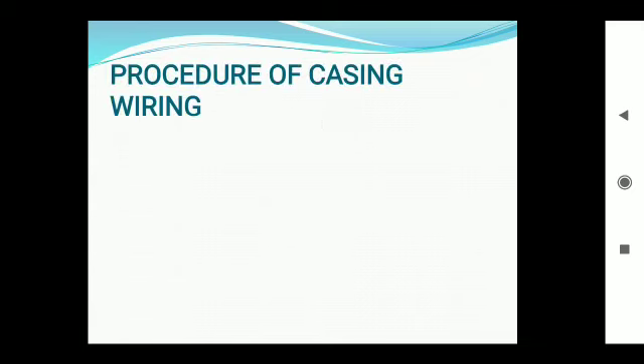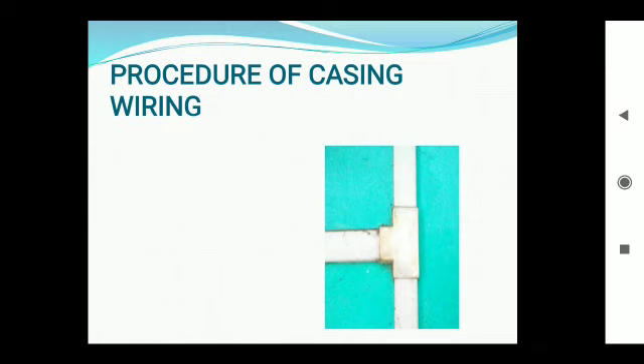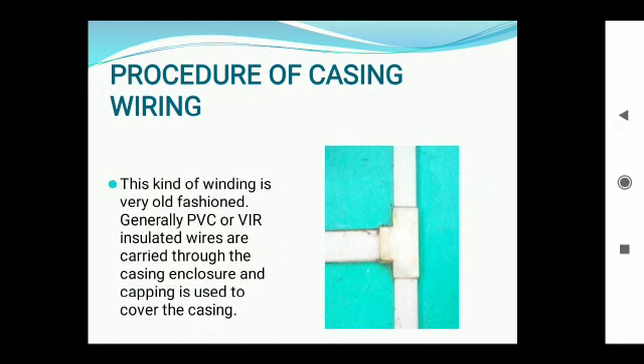Now the procedure of casing wiring. You can see the image of a casing wiring. These are the caps which are connected over the case, and here is a T joint between two wirings, between a horizontal and a vertical run. This kind of wiring is very old fashioned. Generally PVC insulated wires are carried through the casing enclosure, and capping is used to cover the casing.